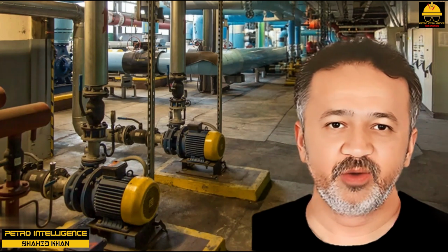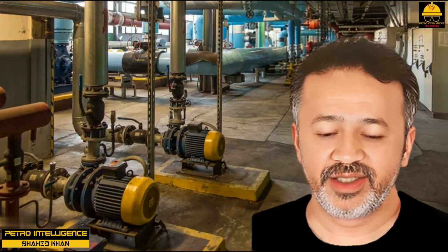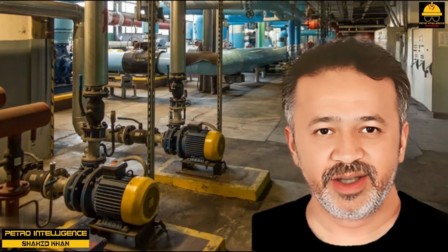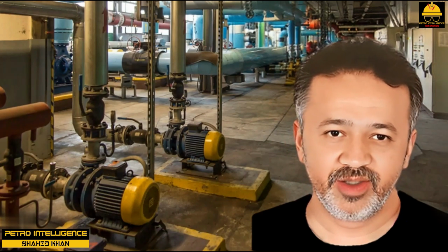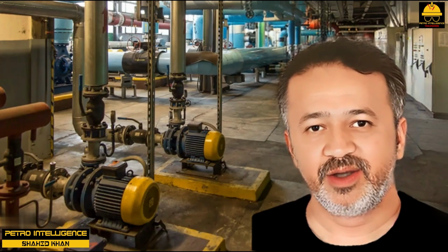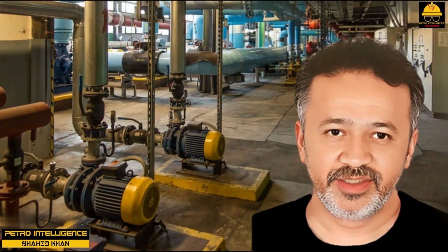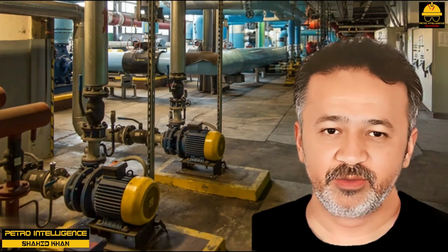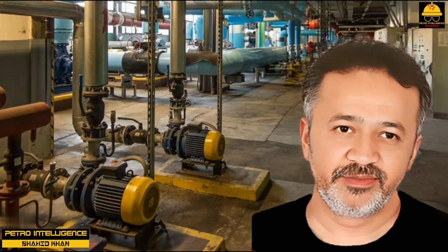The amp meter on the motor breaker indicates the amps being pulled by the motor. Next to this meter should be a tag or a penciled number indicating the full load amp, FLA, point for the motor. Above the FLA point, the motor should trip off. Operating the motor substantially above its FLA point will burn up the motor's windings. This is not quite true.